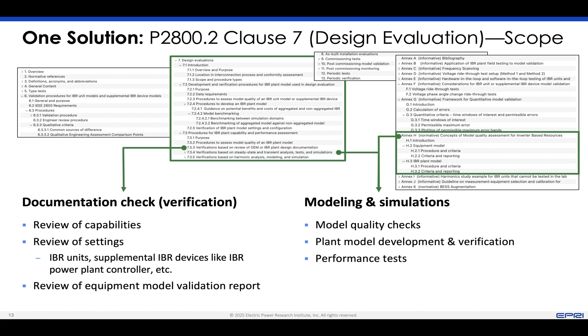So we're not saying that this is the one and only solution. This is just one solution, how to go about these things. The intent of these performance tests is to assess performance of a given plant connecting to a specific grid connection point that has certain characteristics, for example, in terms of weak or stronger grid, SCR ratio, and X to R ratio, to run some tests that assess whether the plant is in conformance with the IEEE 2800 standard or not.